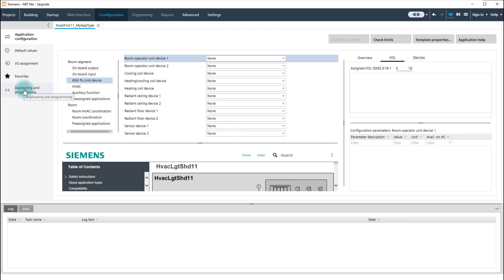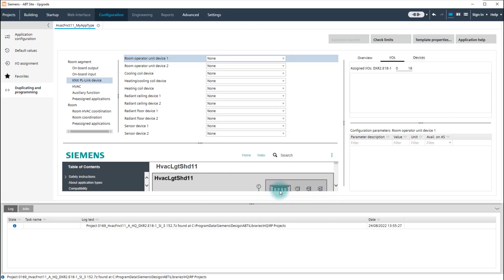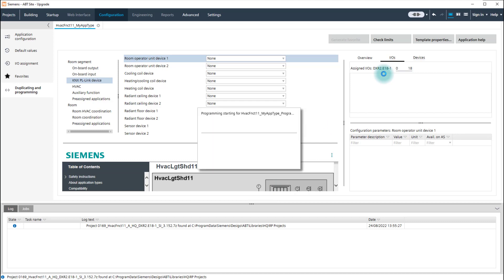Now simply pressing 'Duplicate and Programming' here will start the application programming — the room programming editor in ABT Site. I give it a proper name, and now the ABT Site room programming editor starts with an empty DXR2 E18 controller.